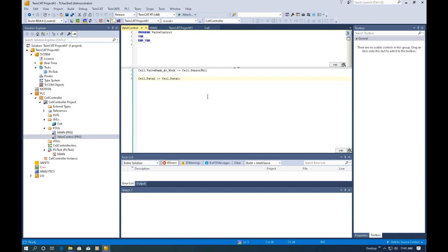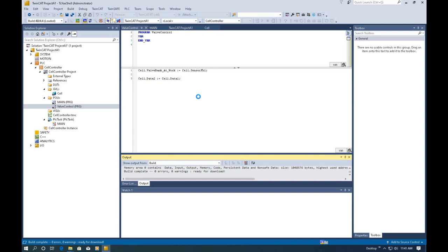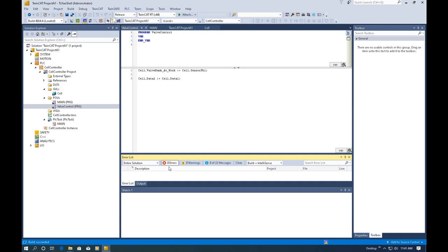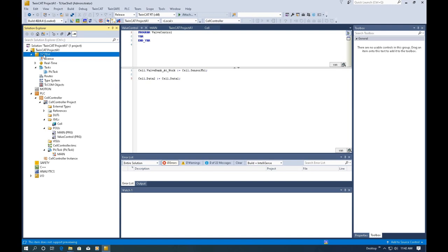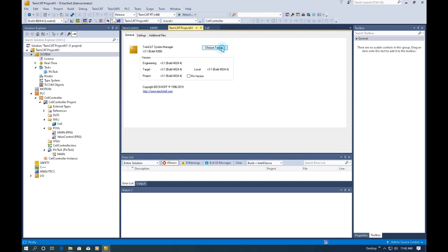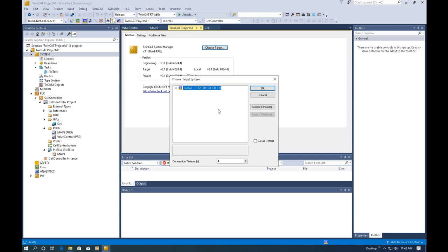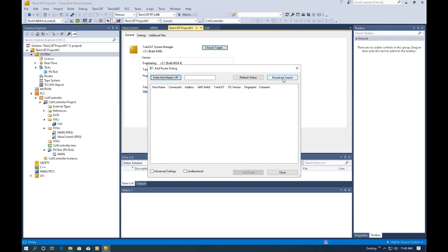If you have an actual controller, the first thing to do is build your project and make sure there are no faults or errors. If you have an actual controller, double-click the System node, select 'Choose Target', and the system will search for an actual controller you are connecting with. You can scan for the controller, and if you don't know its IP address, go to 'Search Ethernet' and select 'Broadcast Search'.